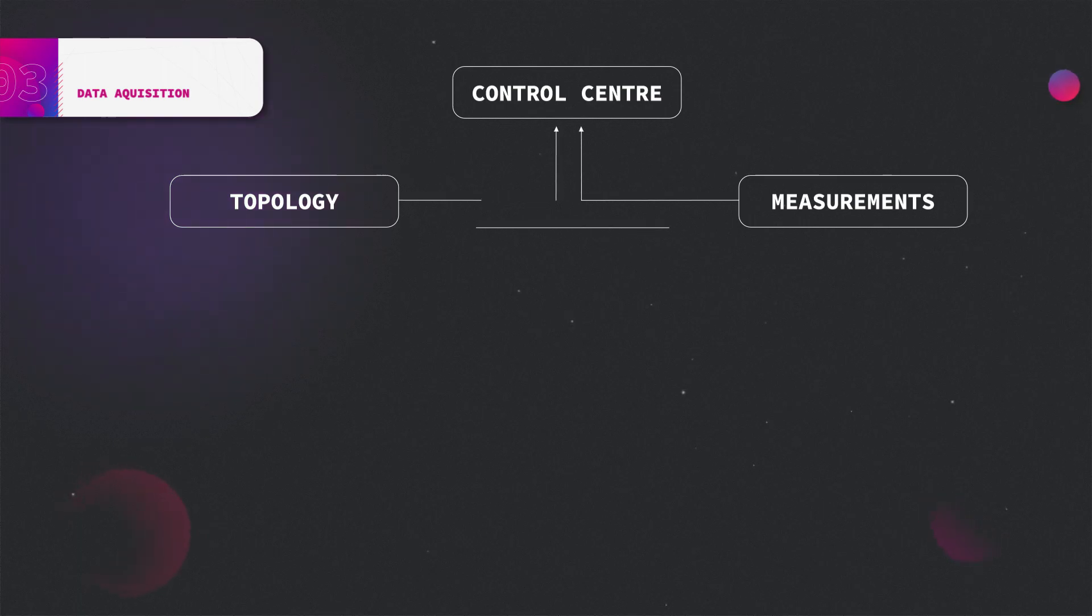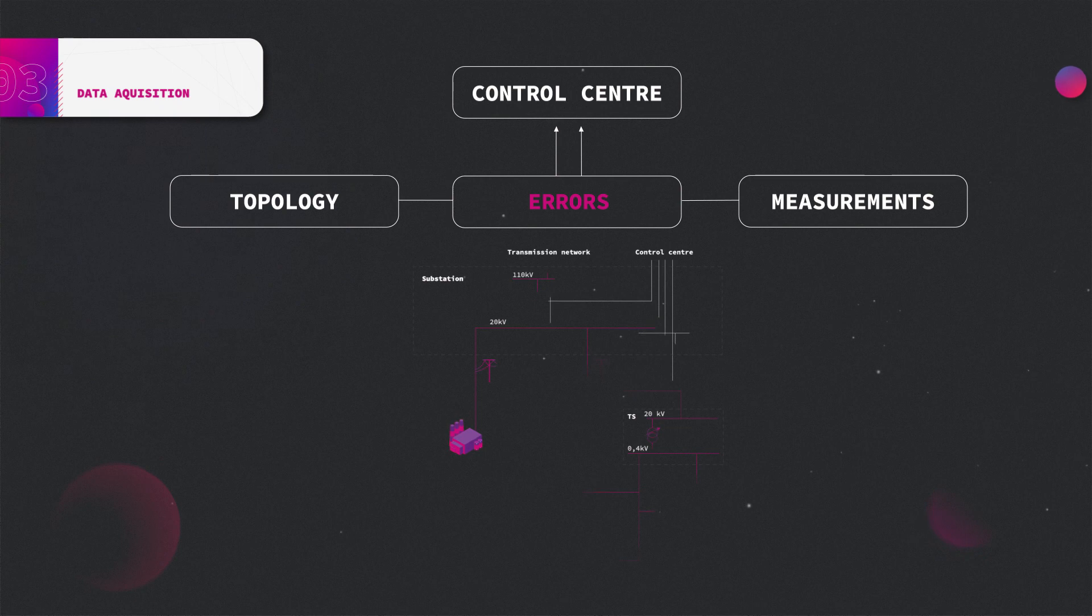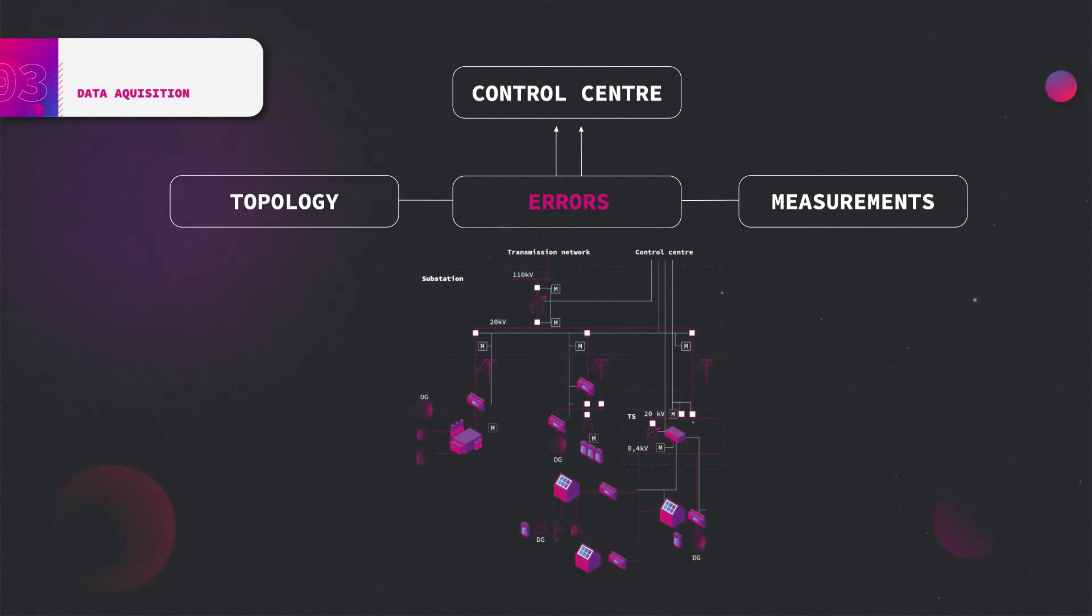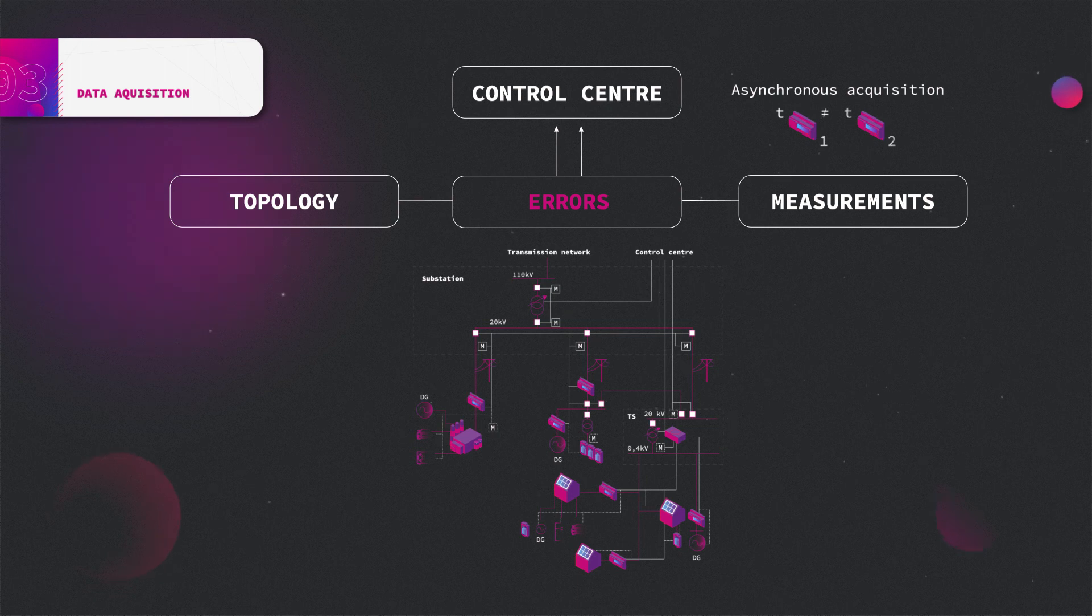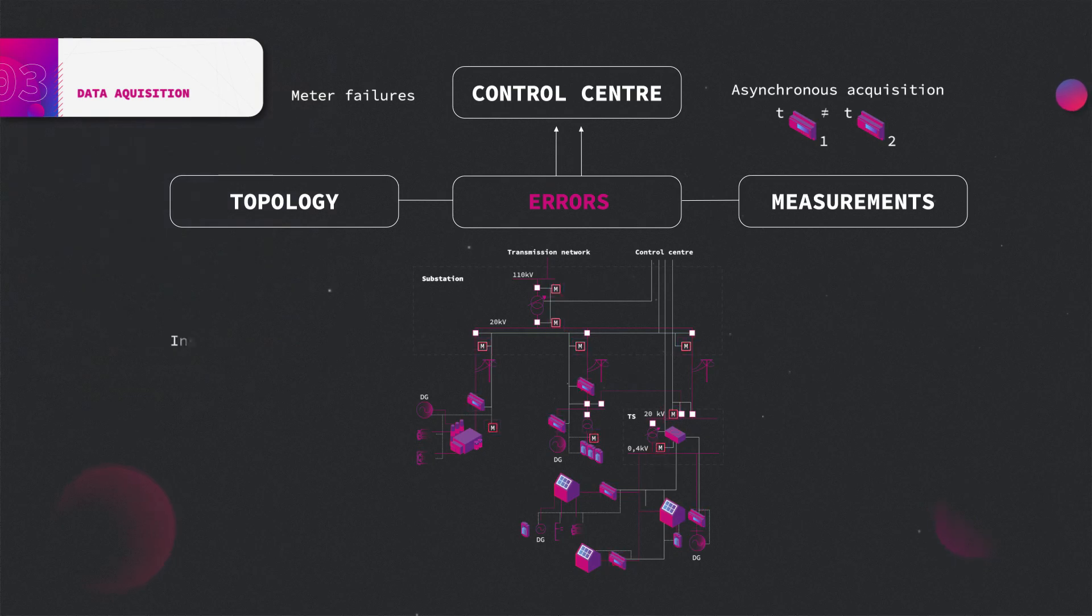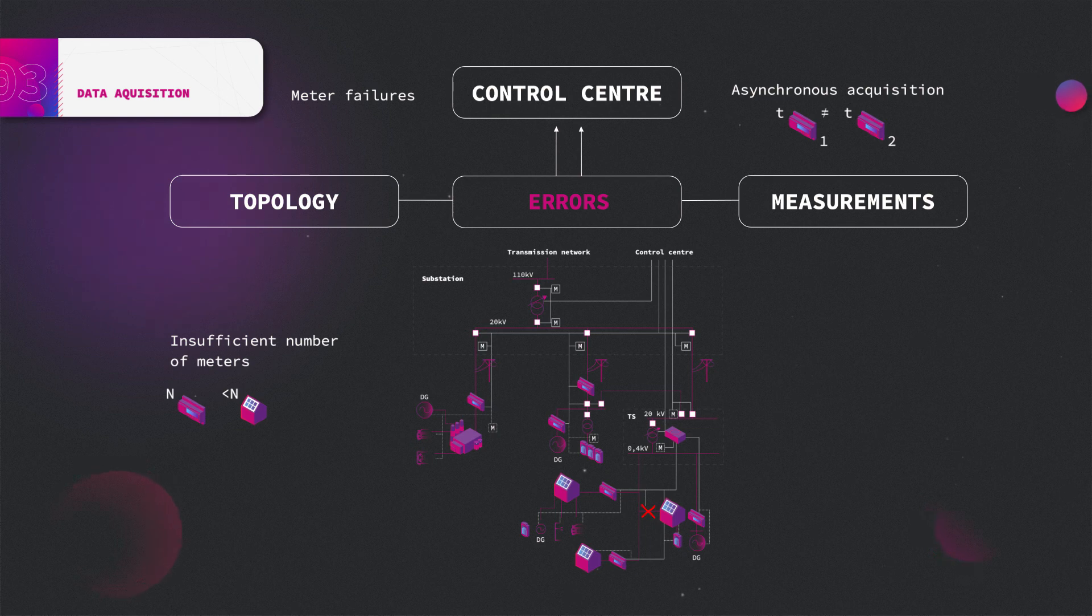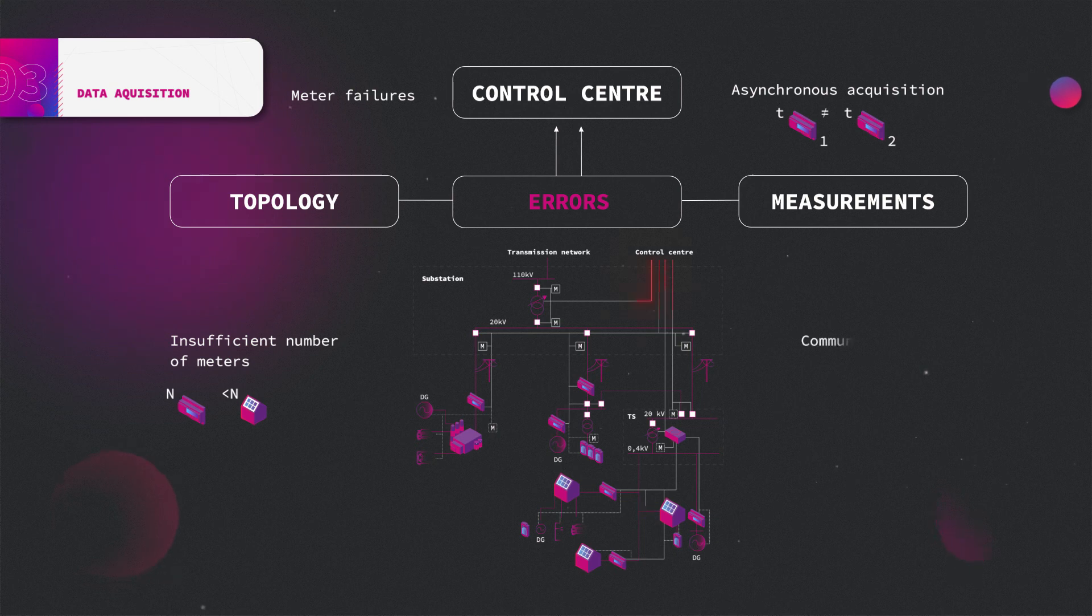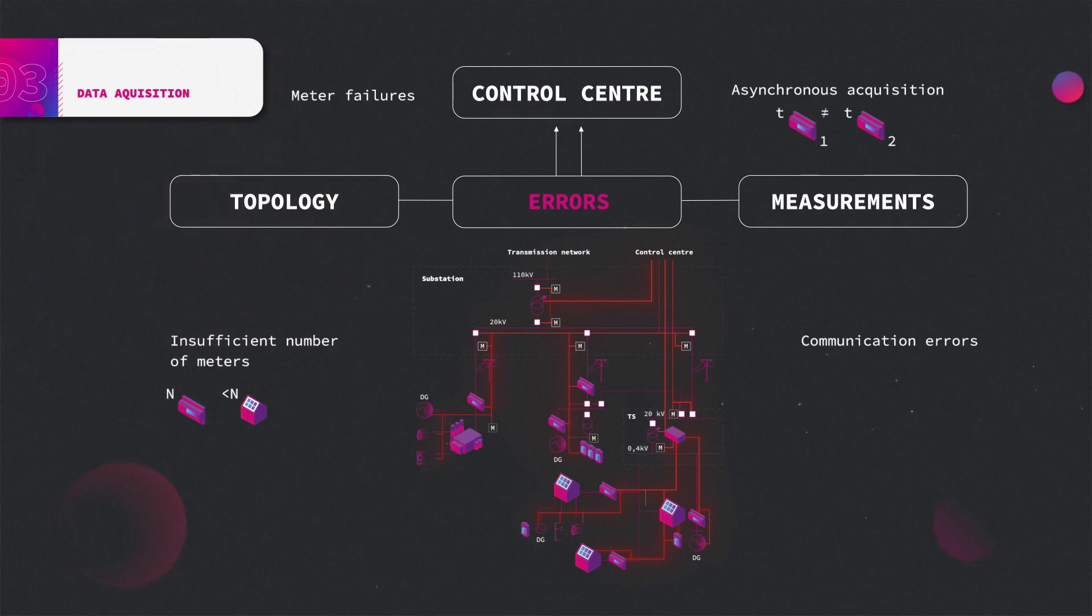Unfortunately, raw data usually has some flaws caused by asynchronous measurement acquisition, measurements on different locations are acquired at different time instances, meter failures due to hardware or software errors occur from time to time, insufficient number of meters, some locations of the network are not covered with designated meters due to economic or technical reasons, and communication errors. Communication paths fail due to congestions or equipment failure.